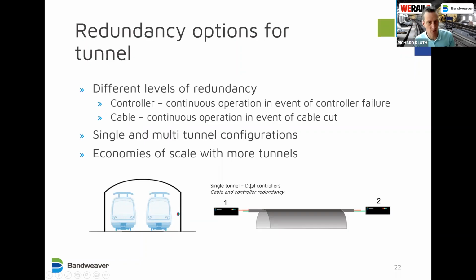This first example I'll work through shows a single tunnel and two controllers. But what we'll see is that as we go through to multi-tunnel configurations, you get economies of scale with more tunnels. That means you don't need two controllers per tunnel to have redundancy. So going back to this example, we have a single tunnel and a controller on either end of the tunnel. We have a single cable running in the tunnel, but this cable has two fiber optic cores at the center. So the red one is attached to system 1 and the green core is attached to system 2.